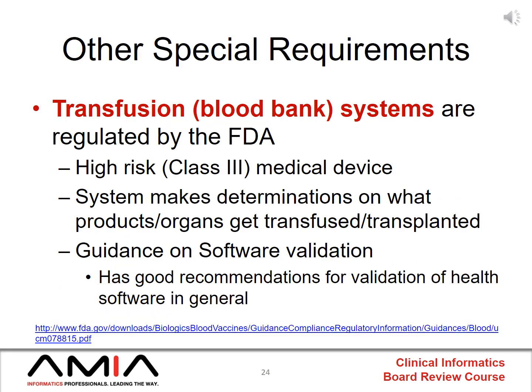The last aspect of laboratory regulations that will be covered in this lecture include the fact that transfusion or blood banking information systems are regulated by the United States Food and Drug Administration. This is because these information systems are making recommendations and determinations on what blood products or organs or tissues are getting transfused or transplanted into patients, and therefore they're classified as a high risk or class 3 medical device.